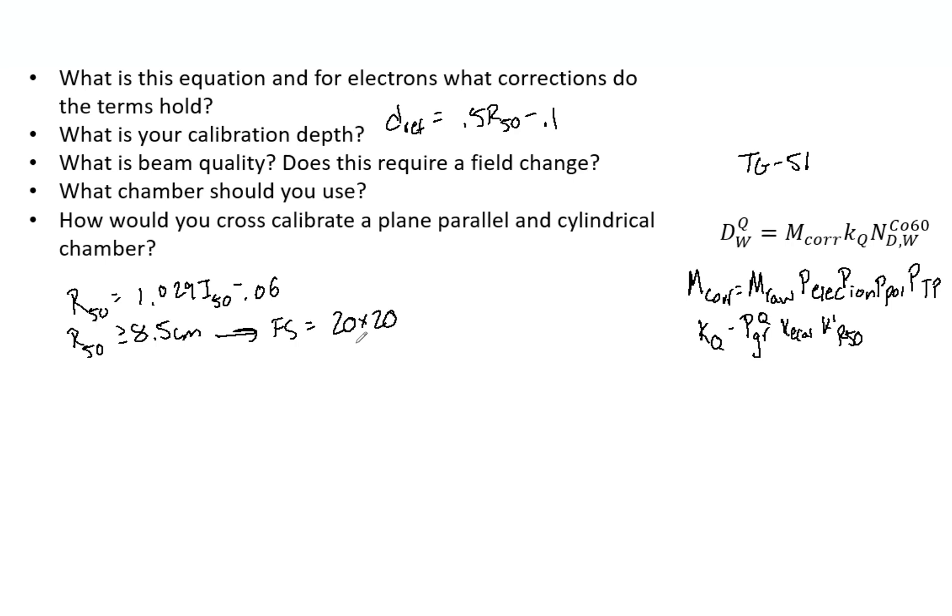Now, what chamber should you use? For electrons, it's recommended to use a plane parallel because it minimizes the variations in P-ion, P-pole, and P-gradient with depth. For plane parallel, P-gradient is equal to 1. And if you have 10 MeV or less, a plane parallel is preferred. 6 MeV or less, plane parallel is required by TG-51.